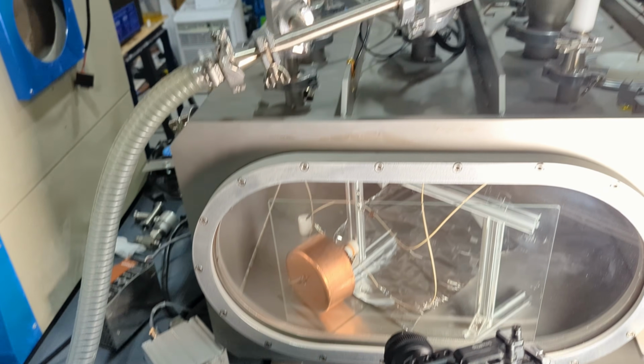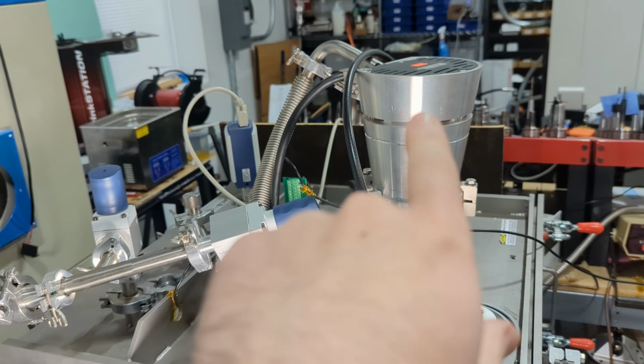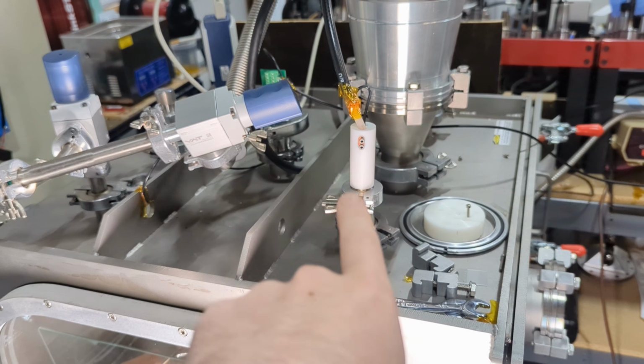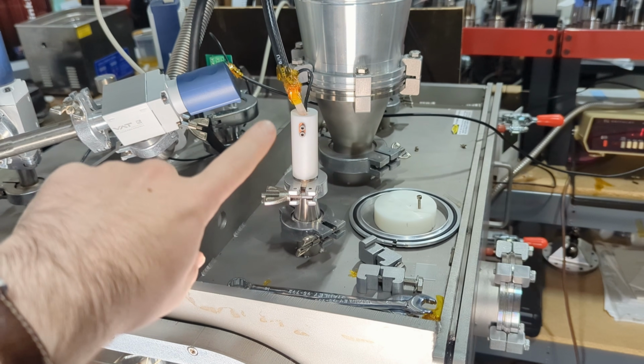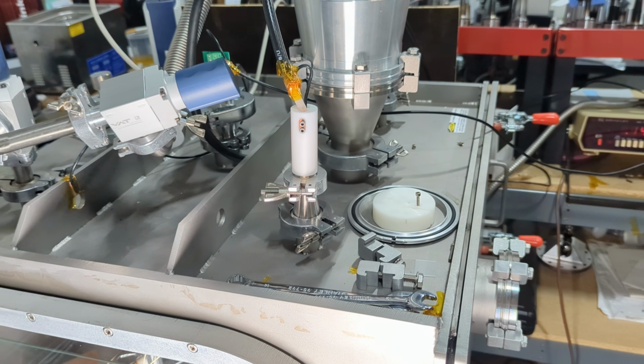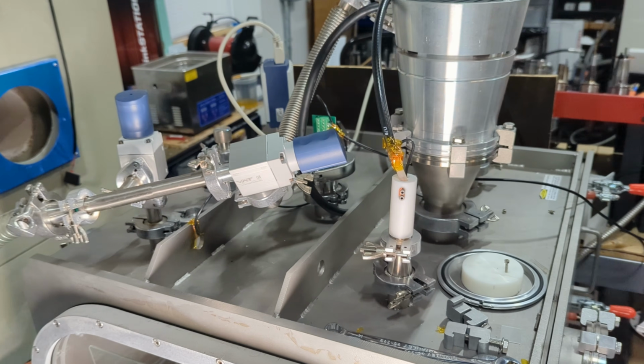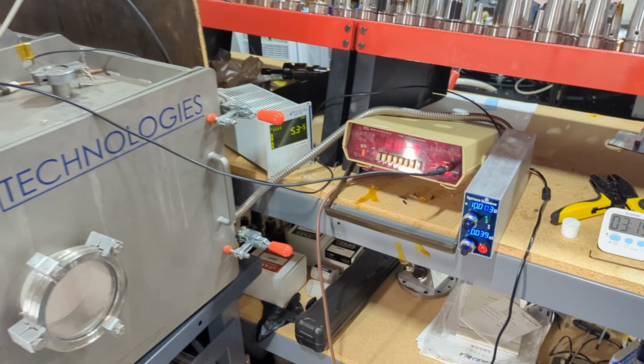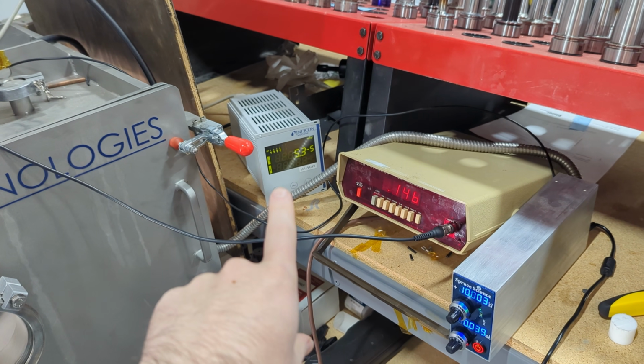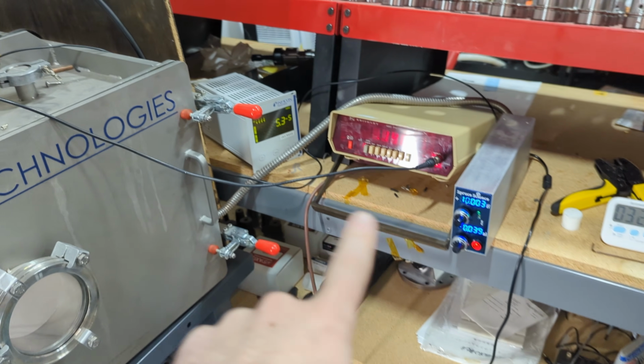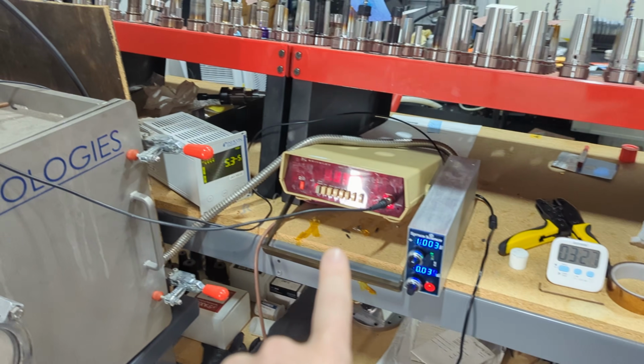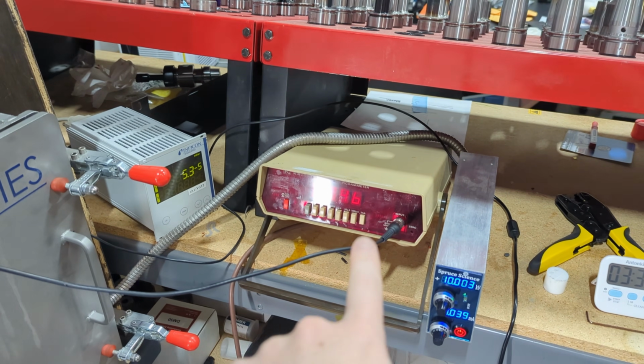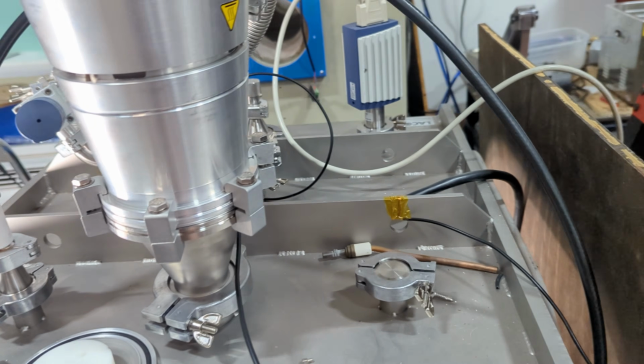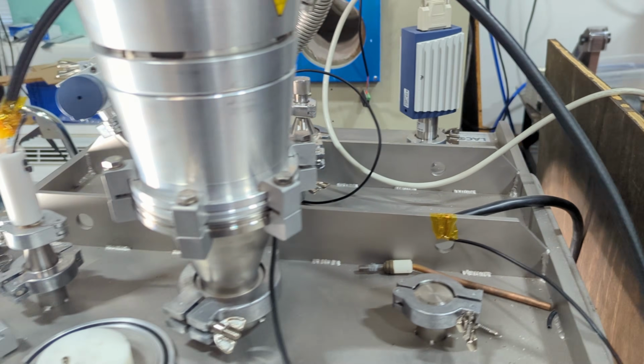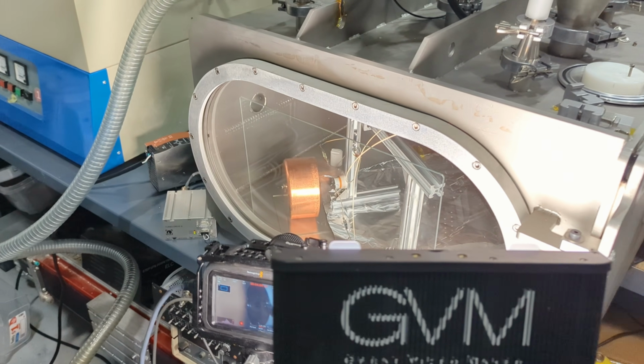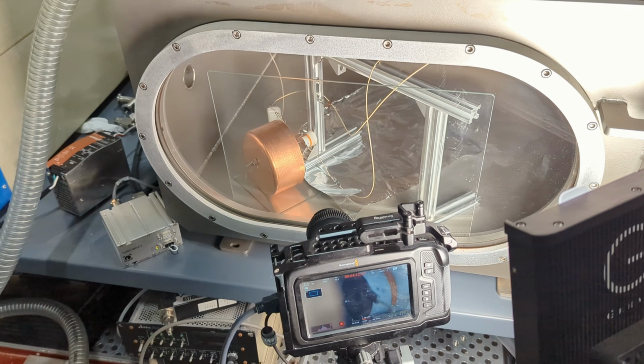Turbomolecular pump controller there. Valves, etc. Turbo pump. This is the high voltage feed through with a kind of custom Teflon and copper connector because it didn't come with one. And then over here we've got some electronics. There's the vacuum pressure gauge, the high voltage power supply, and can't really see that because of the glare, but that is a pico ammeter, which is going to a feed through right there. And that's being used to collect the current or measure the current from the Faraday cup.